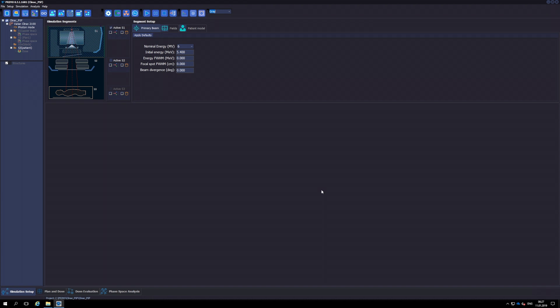In this simulation we will use a nominal energy of 6 MV. After choosing it, we need to enter the initial beam parameters, namely the initial energy of the electrons impinging the tungsten target, the full width half maximum of the initial energy, the focal spot size and the beam divergence. These parameters are determined by comparing depth and lateral dose simulated profiles with experimental data. In the next video it will be shown how to do this comparison. More details on how to find the initial beam parameters that reproduce a given Linac can be found in the user's manual of Primo.